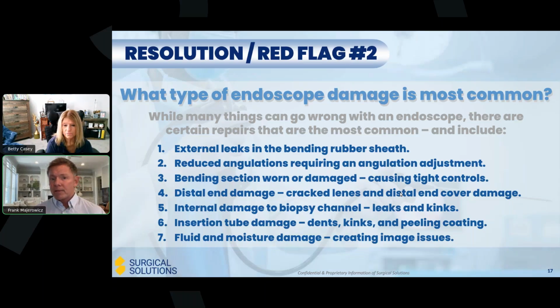External leaks in the bending section sheath. That's at the distal tip of the insertion tube, the last 5 to 6 inches. The outer sheath is made of a thin rubber material. It's very prone to getting cut, pinholes and leaks in that area. Definitely an area you want to keep an eye on and keep sharp objects away from that particular part of the endoscope.